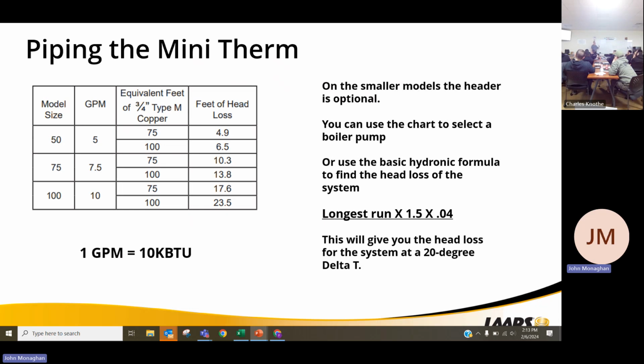When you get into cast iron and convectors, there's books and charts out there that'll show you how many BTUs are per square foot of radiation that's in there. But if we're trying to figure out our pump, we take our longest run, furthest point from the boiler to the last radiator, times that by 1.5, times that by 0.04, and that gives you your head loss.